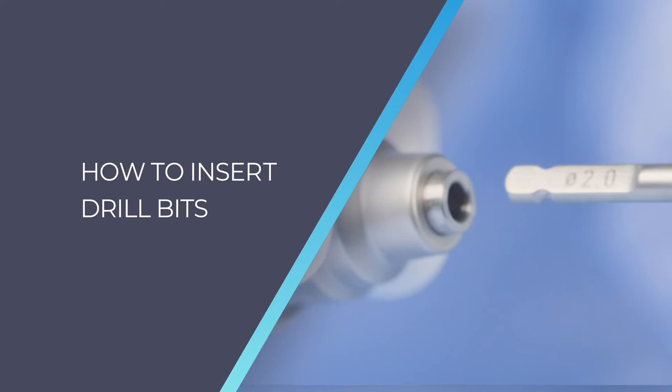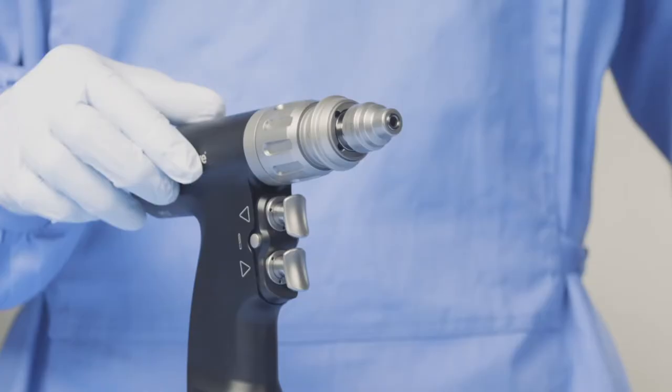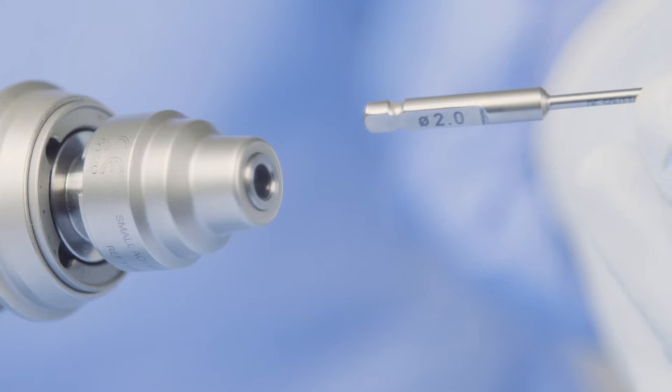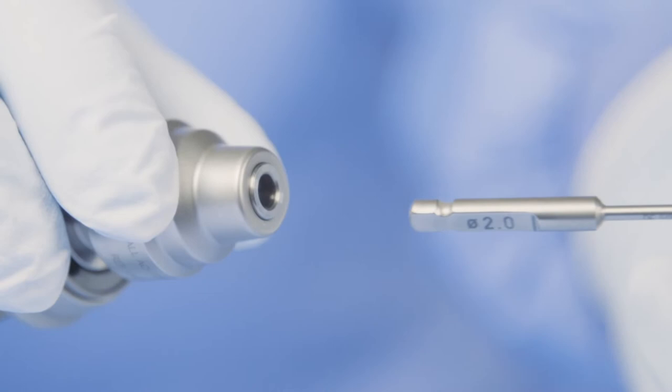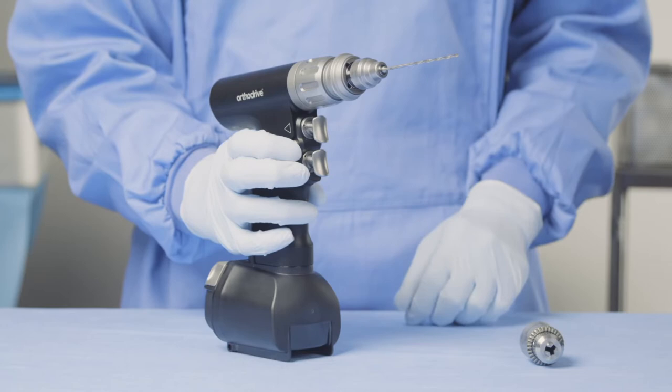If you take your AO quick couple attachment and place it into your tool, get an AO drill bit, which is characterized as a half moon shape with a notch cut out. Pull back on the collar on the attachment and slide the drill bit in until it sits into place. Release the collar to lock.